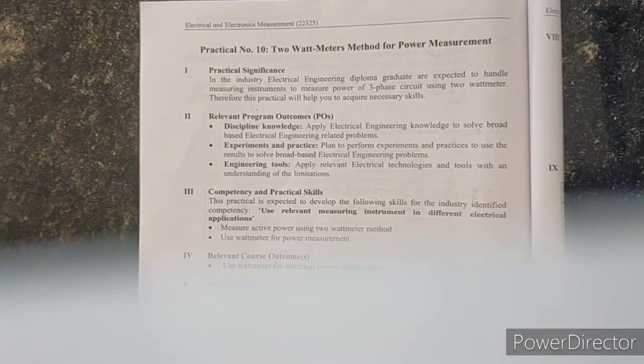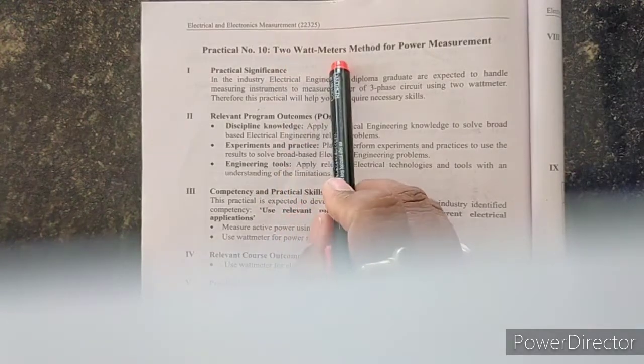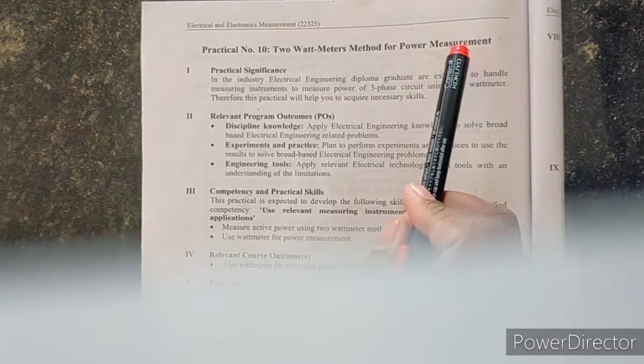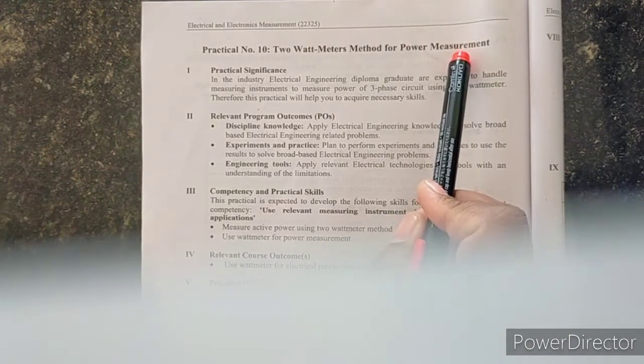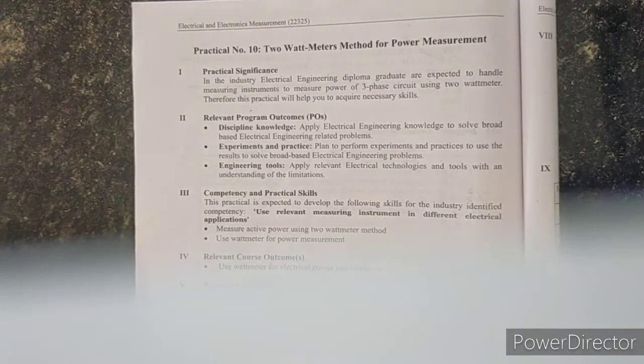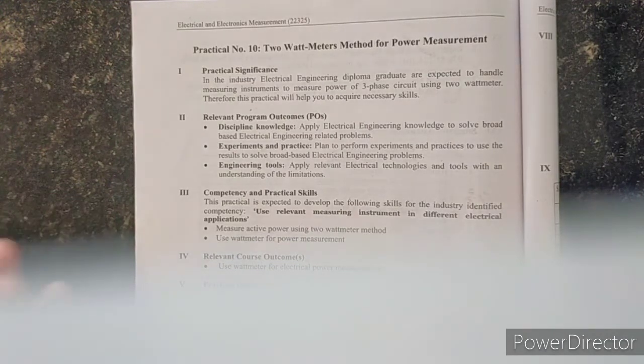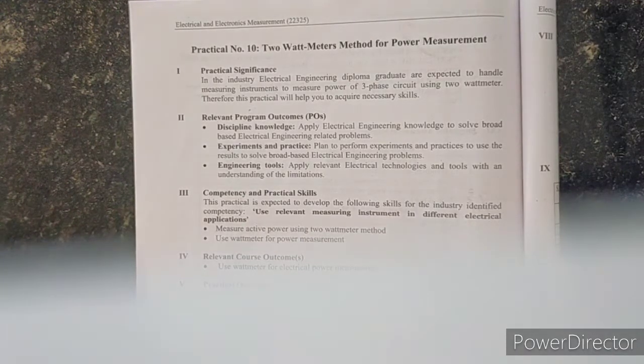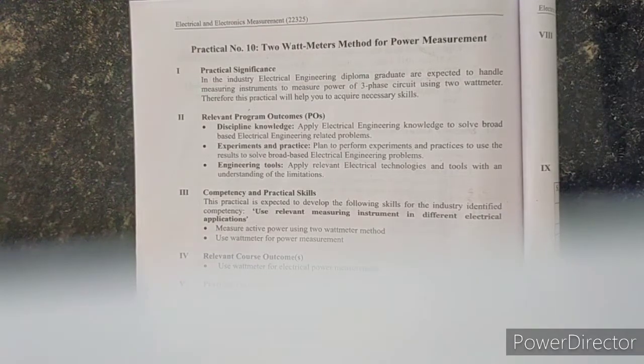Hello students, today we will see practical number 10 from the EEM subject. The aim of the practical is the 2-wattmeter method for power measurement. In this practical we have to measure the active power using the 2-wattmeter method. There are 3 methods for power measurement: 1-wattmeter, 2-wattmeter, and 3-wattmeter. The 2-wattmeter method is suitable for a 3-phase 3-wire system, can be used for star and delta systems, and works for both balanced and unbalanced loads.